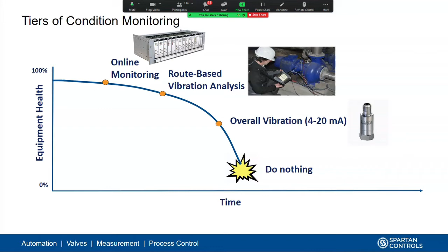We interface those online condition monitoring systems to our SCADA systems and PLCs, so we can get alarms in real time indicating a fault condition has occurred. Online condition monitoring uses the same vibration analysis technology, but does it 24/7, giving us data on a second-by-second basis, much higher fidelity.